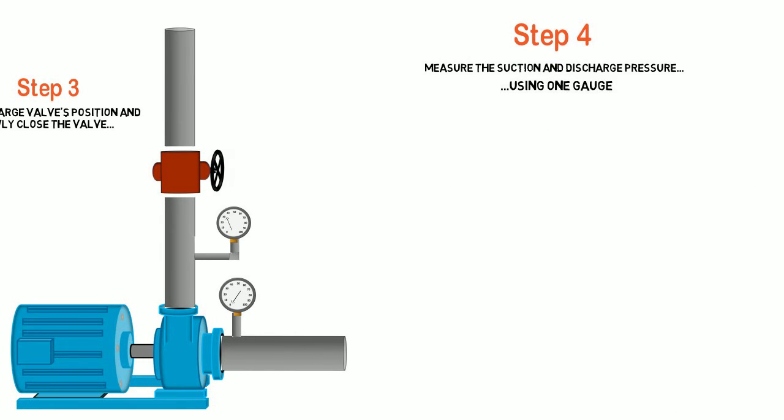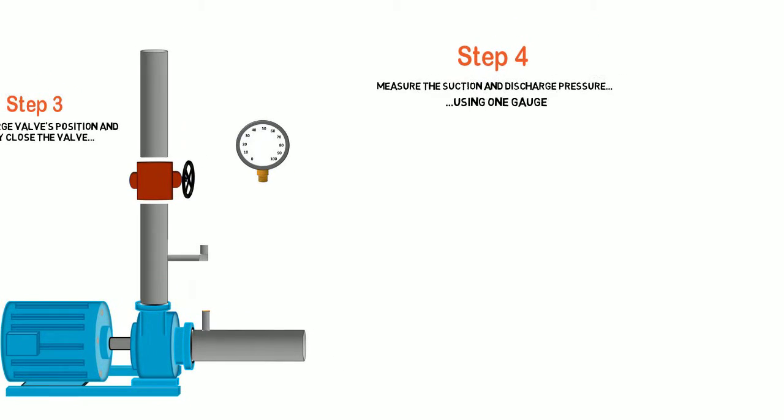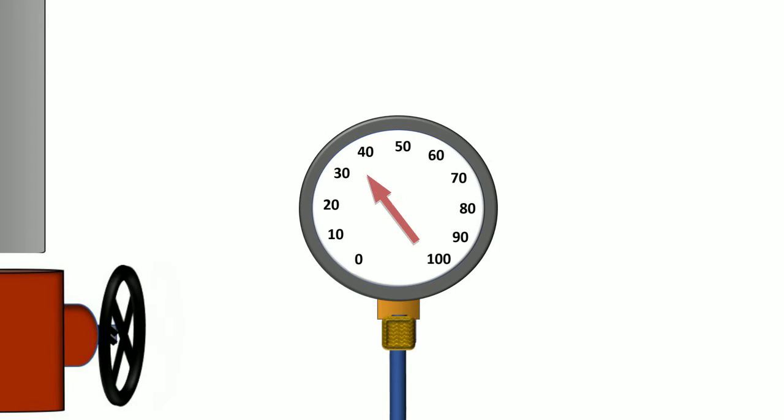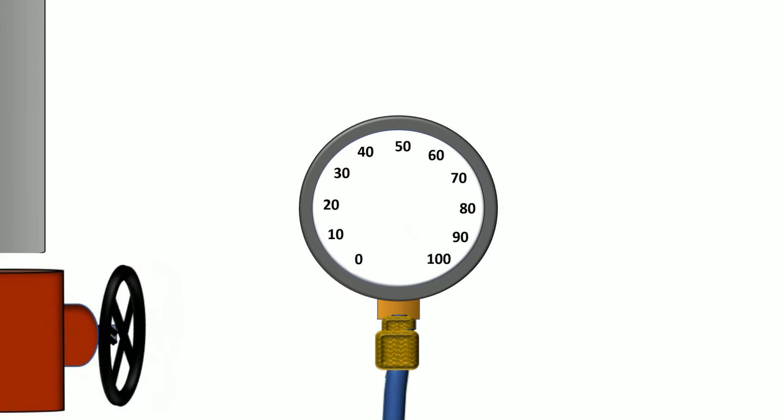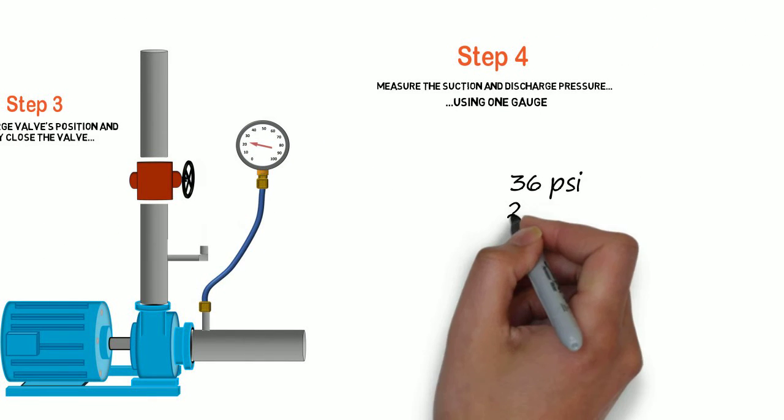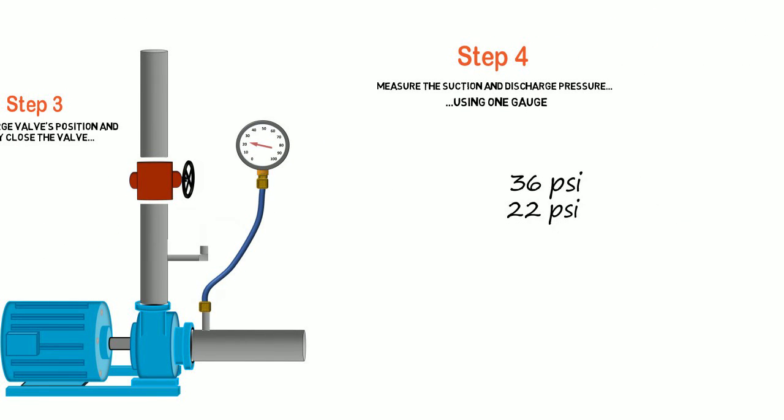Measure the suction and discharge pressures using one gauge, not the gauges that have been bouncing around on that pump for the past decade. Take those off, use one gauge, use a piece of hose, hold the gauge at the same height. First, the discharge. In this example, we've got about 36 psi. Write it down. Now, move the hose over to the suction. Record it. We've got about 22 psi. Write it down.